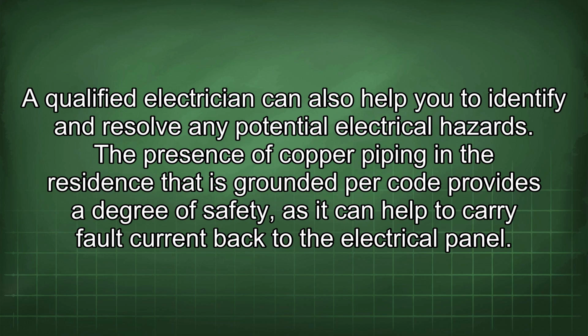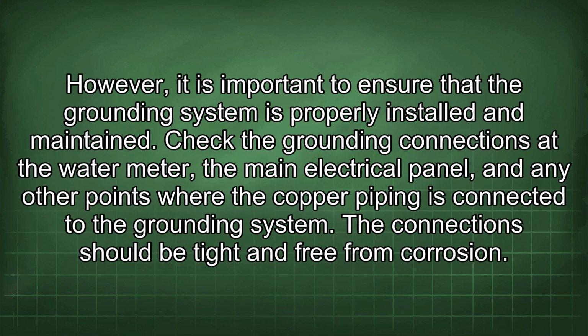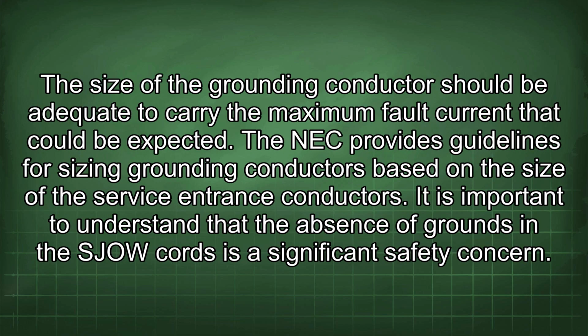The presence of copper piping in the residence that is grounded per code provides a degree of safety, as it can help to carry fault current back to the electrical panel. However, it is important to ensure that the grounding system is properly installed and maintained. Check the grounding connections at the water meter, the main electrical panel, and any other points where the copper piping is connected to the grounding system. The connection should be tight and free from corrosion. The size of the grounding conductor should be adequate to carry the maximum fault current that could be expected. The NEC provides guidelines for sizing grounding conductors based on the size of the service entrance conductors.